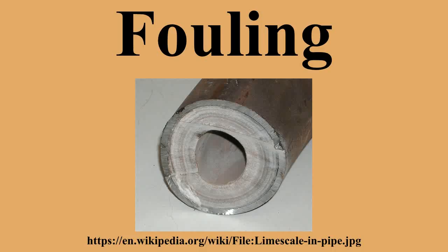Seesaw fouling. Here, fouling loading generally increases with time, but, when looked at in more detail, the fouling progress is periodically interrupted and takes the form of a sawtooth curve. The periodic sharp variations in the apparent fouling amount often correspond to the moments of system shutdowns, startups or other transients in operation.